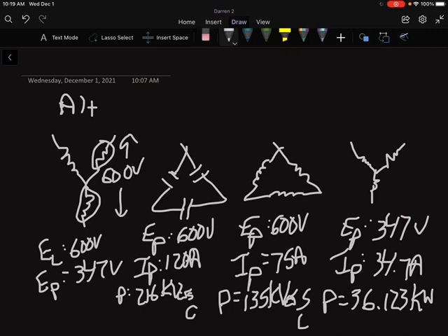When we come into our line values for the resistive load, if we had an amp clamp around that phase and then came up into the line, we're not adding another phase to that. So our I phase and IL will be the same. Up here we know IL is equal to 34.7 amps. And remember, when we're doing vectors, the line current is what's being used when we go to plot it to use Pythagorean theorem.